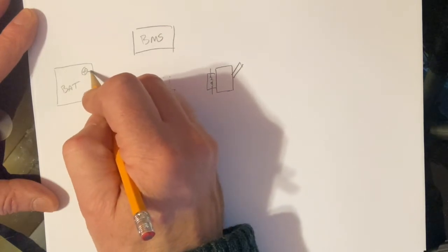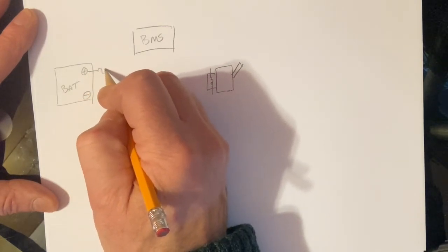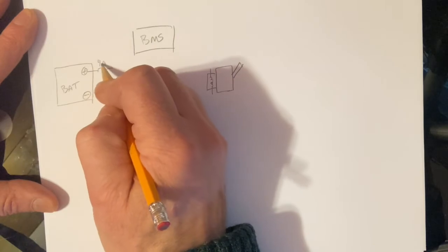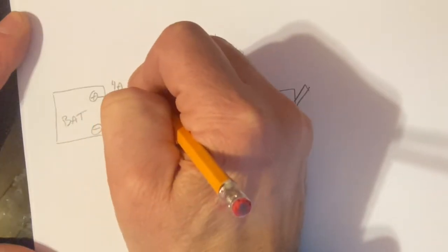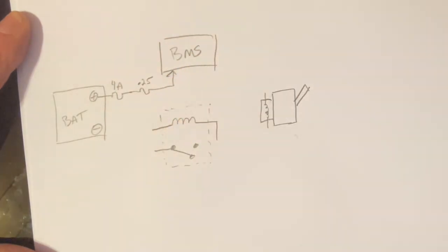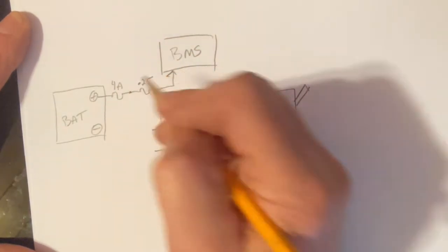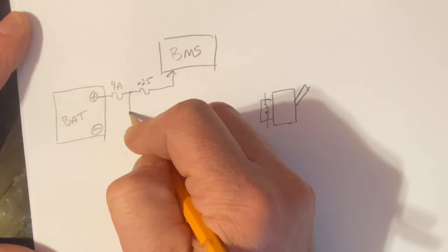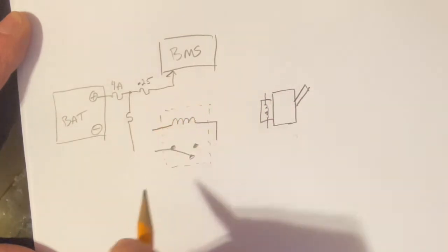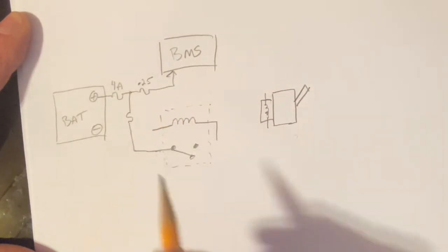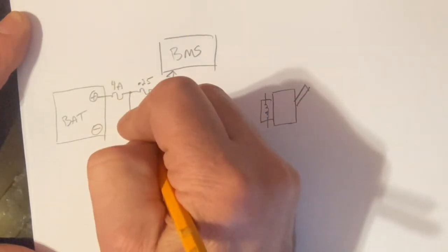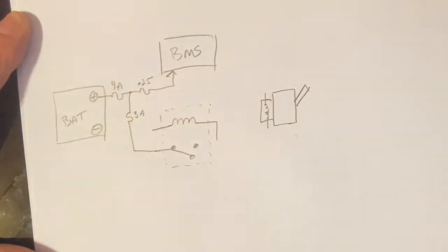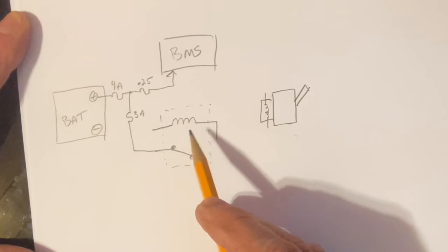So the first thing is we come out of the battery with a main fuse. In this case, it's a 4 amp fuse. This is a 1/4 amp fuse that protects the BMS relays. After the 4 amp fuse, we're going to another fuse, and this will go to the relays. This is a 3 amp fuse. So this is our control circuit relay.